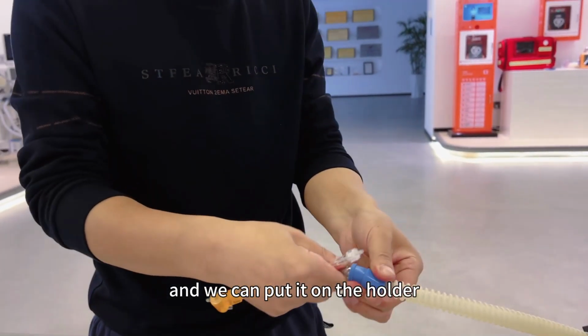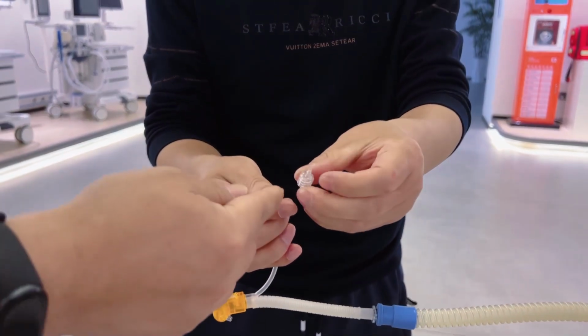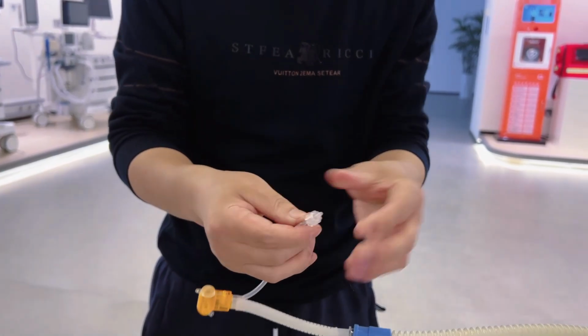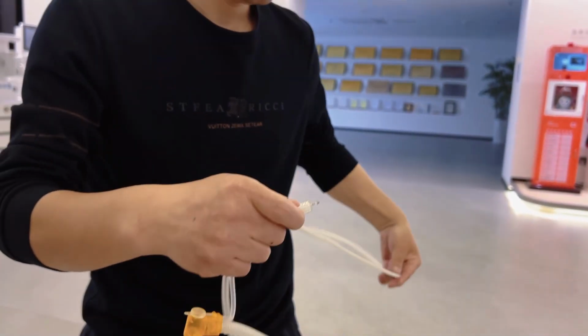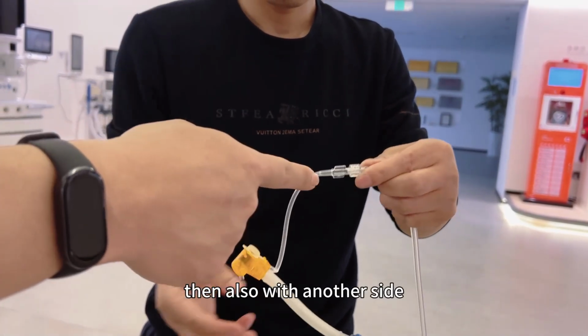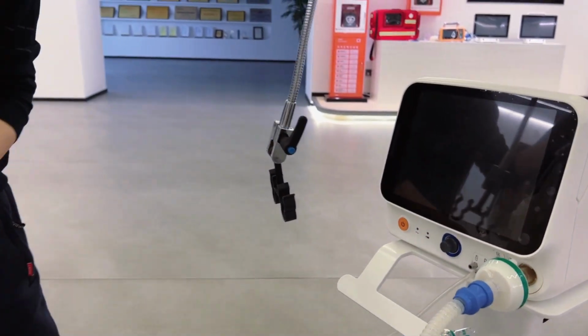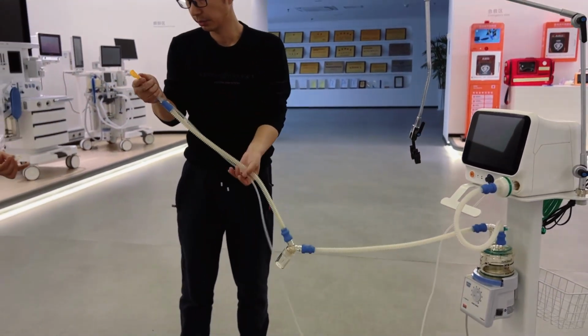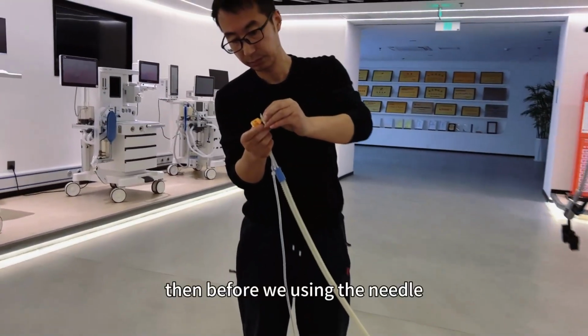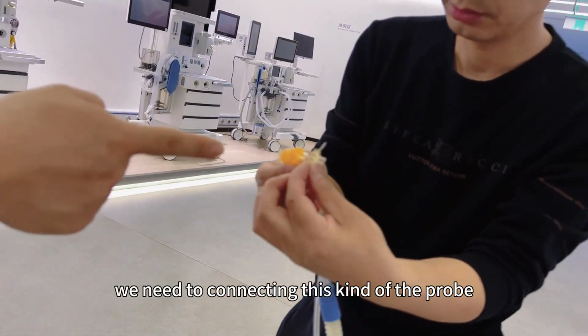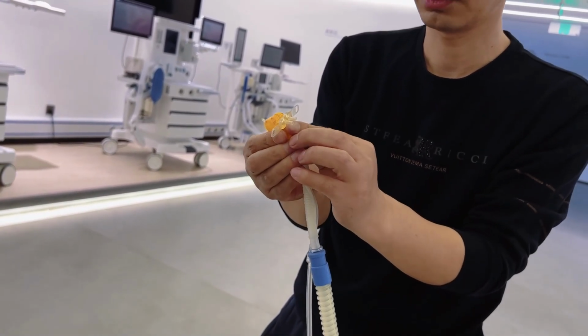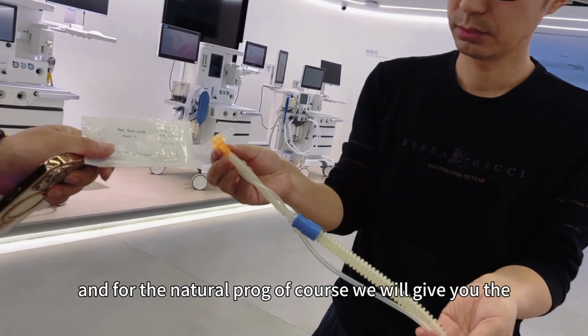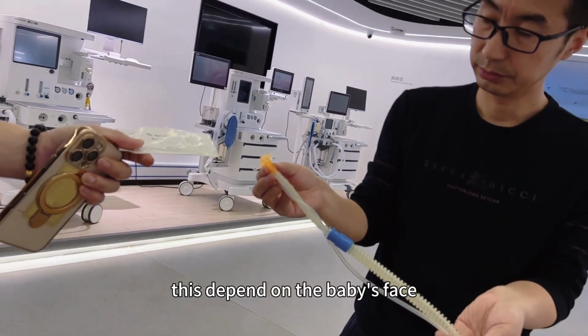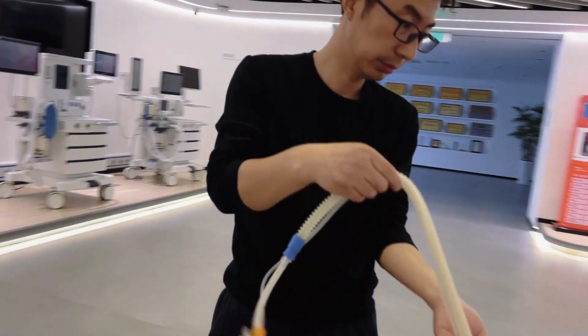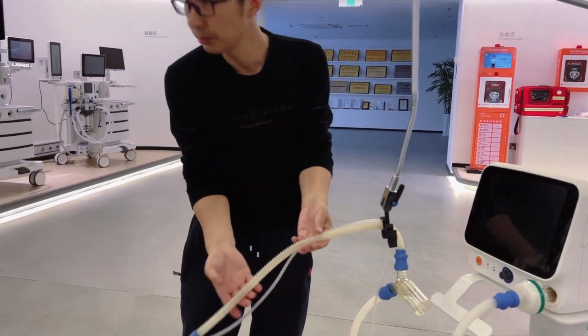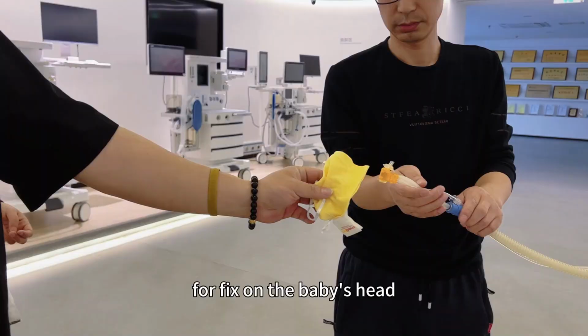Now we connect another pipeline with another side of the water trap. And we can put it on the holder. And here, connecting this small item with here. Then also with another side of the pressure sampling tube. Then before using it for the neonatal, we need to connect this kind of nasal probe. And for the nasal probe, of course, we will give you different sizes which you can choose. This depends on the baby's face. And also here, the helmet for fixing on the baby's head.